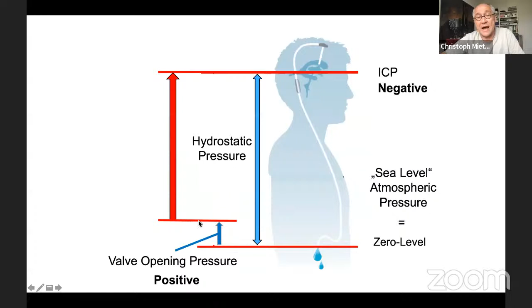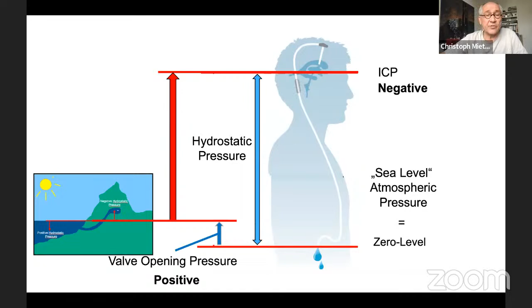Now, in the upper position, the valve is still doing the same. The zero level would be, let's say, at the upper abdomen, and from there the valve shifts this zero level a little bit higher, and here this is the zero level. From here going up, it's becoming negative. So this hydrostatic pressure has to be counterbalanced, and only this part can be taken over by the valve. With this valve, it would establish a significant negative pressure within the ventricular system. So maybe this helps again to make it clear.